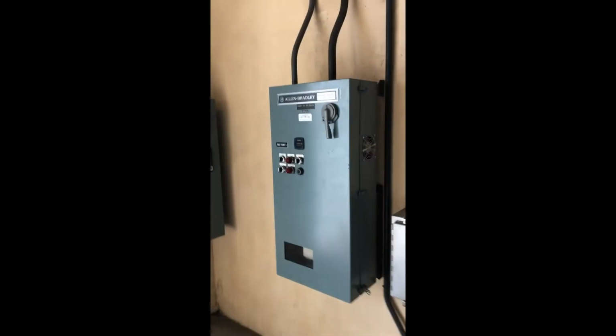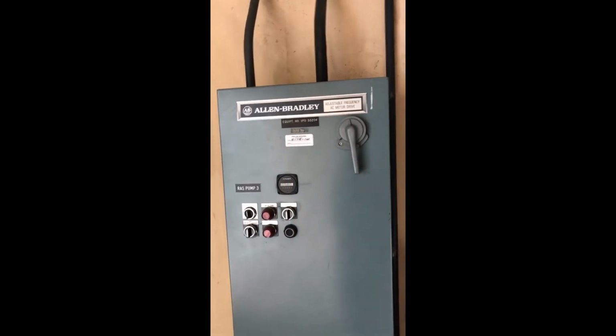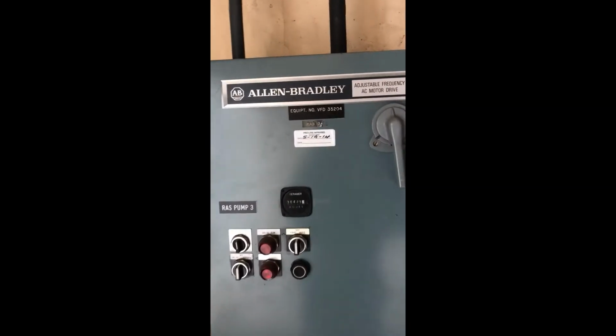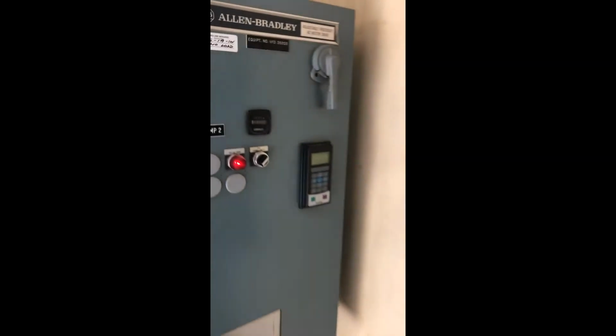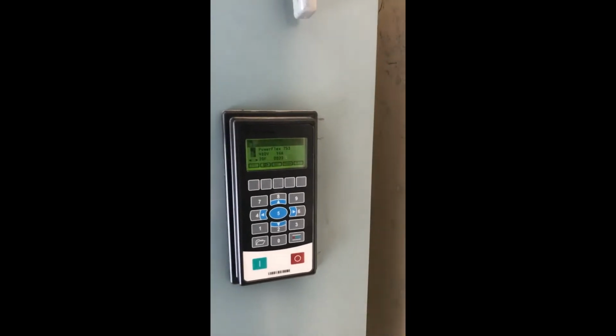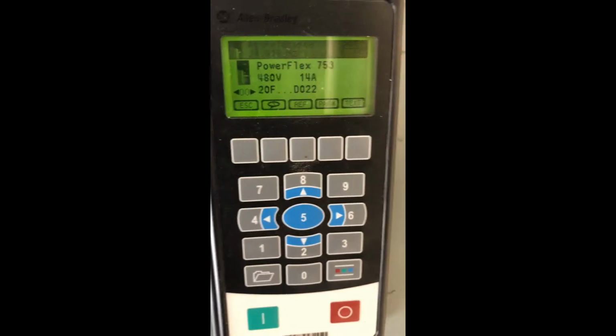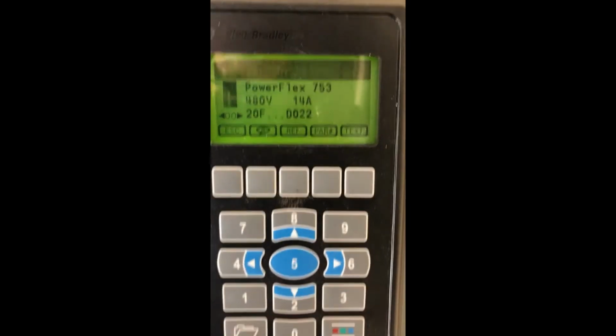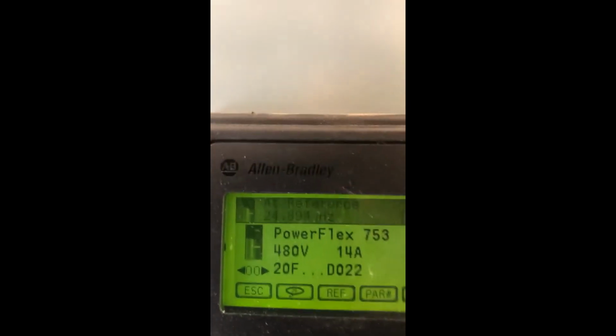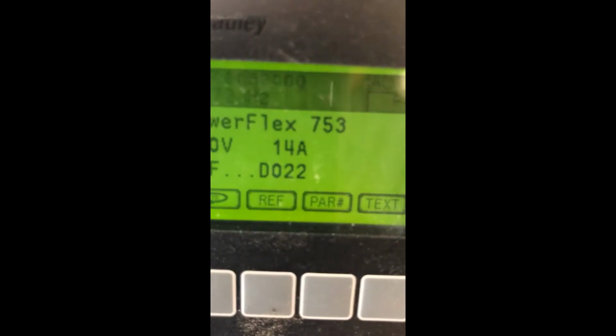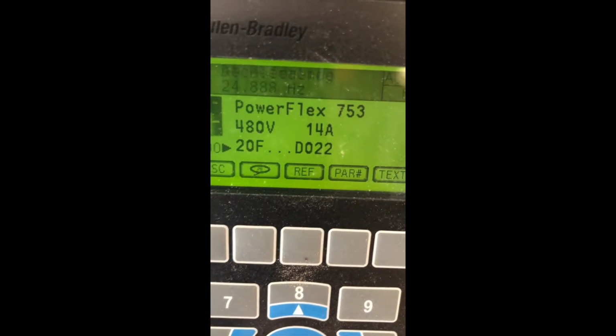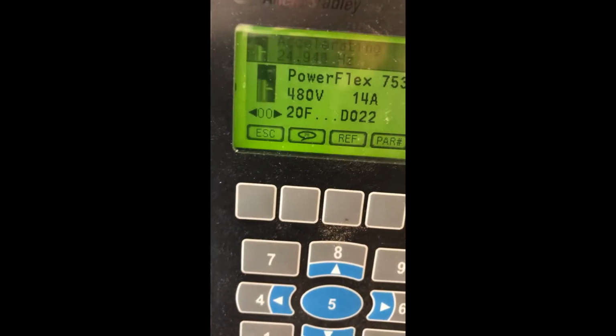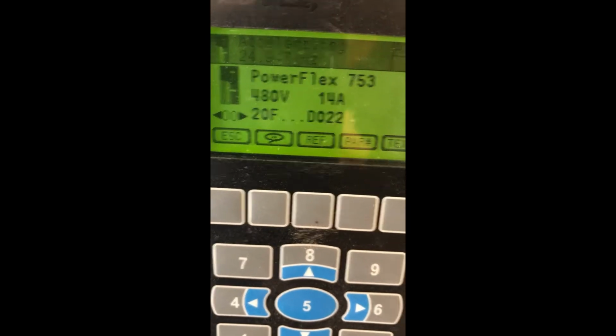Here are some variable frequency drives. These are for our return activated sludge pumps, Allen Bradley. This is called the HIM. It's where we can get some information. I think I can get in here where you can see how many hertz this particular motor is running at right now. Kind of hard to see. So it's up on the top bar.